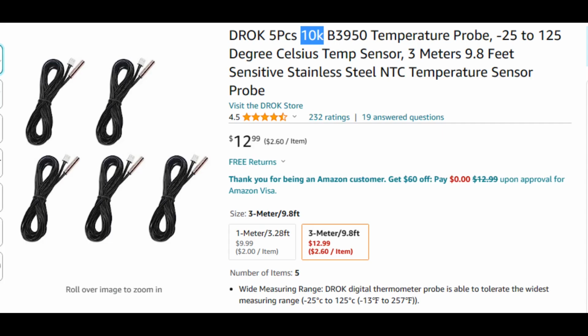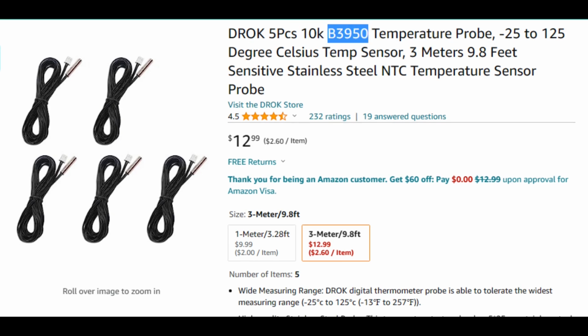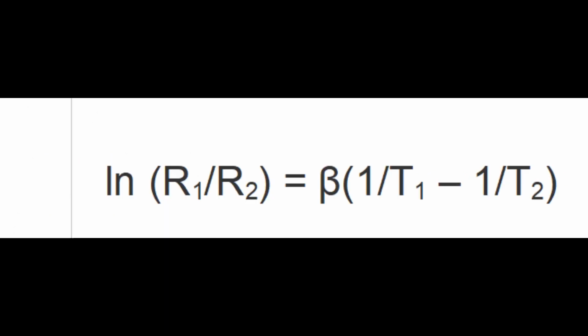This thermistor has a resistance of 10,000 ohms at 25 degrees centigrade and a temperature coefficient, or beta, of 3,950, from which you can calculate the resistance at any temperature using the formula: natural log of R1 over R2 equals beta times (1 over T1 minus 1 over T2), where T1 and T2 are any two temperatures expressed in degrees Kelvin, and R1 and R2 denote the resistance of the thermistor at those temperatures.